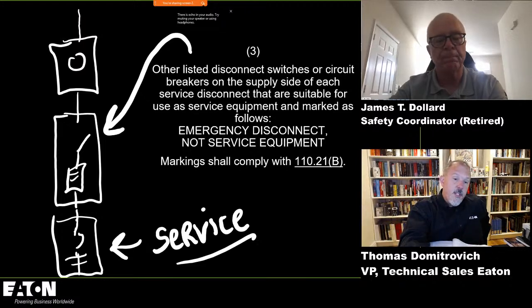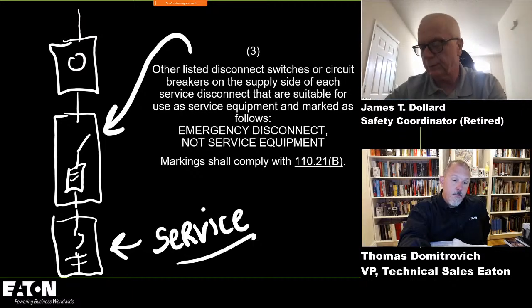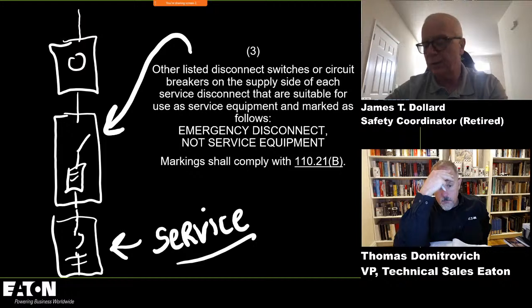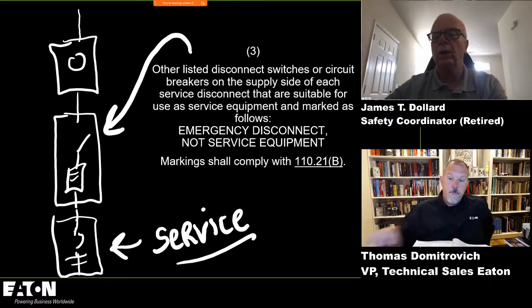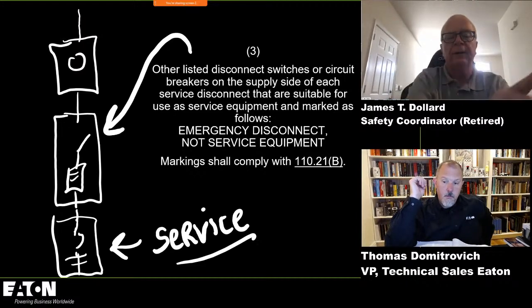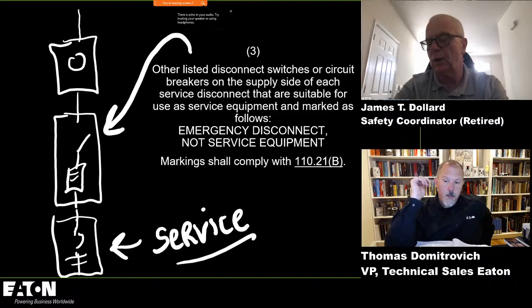Yeah, and you would have to bond the enclosure, obviously. The enclosure is going to be bonded because the grounded conductor in your meter is bonded to the enclosure. That's going to be done. But you're going to need to get a grounding electrode conductor in there, and then you're going to need SER. You can't use SE, and you can't use two insulated conductors and the concentric. If you consider that to be service entrance equipment, you're going to need 3 insulated conductors, and then the concentric can be your equipment grounding conductor. We went through all of that, and this is the most cost-effective way to do it. If we force you to make all of these service equipment, there's no net benefit. In fact, you're going to buy main lug only panelboards.